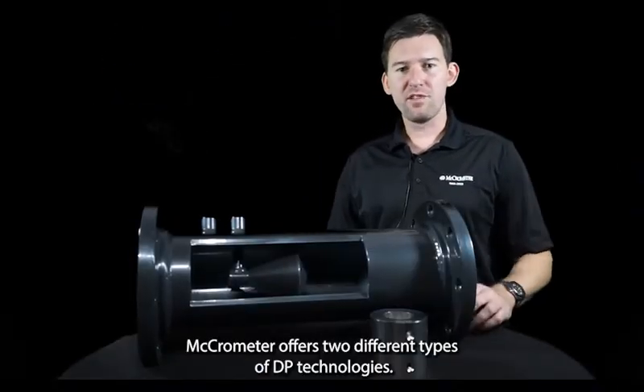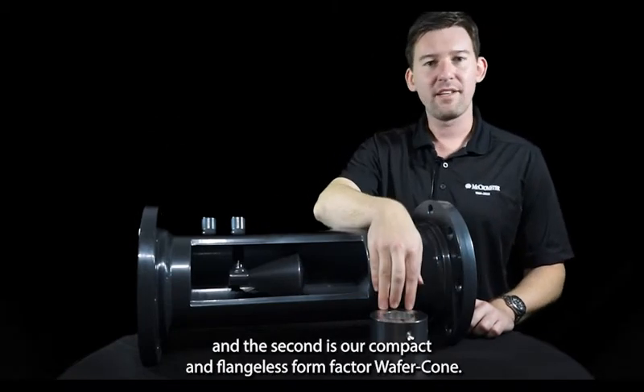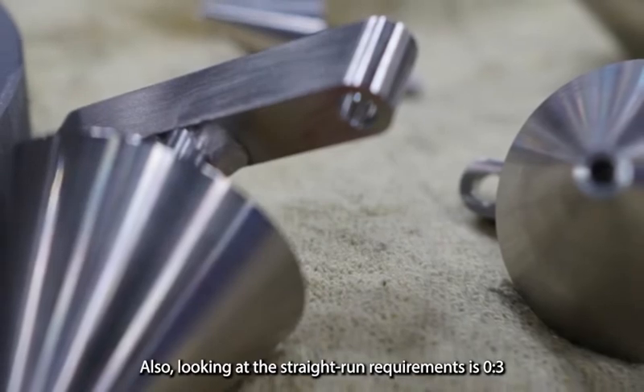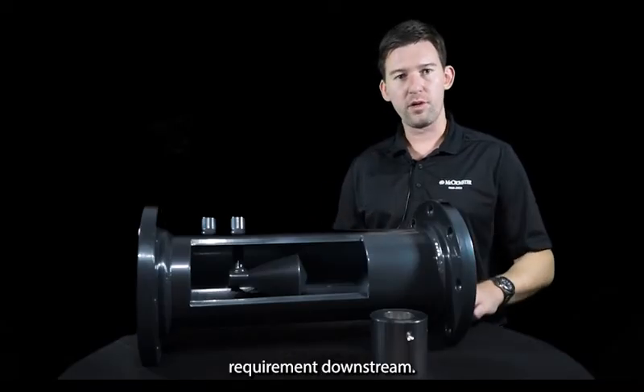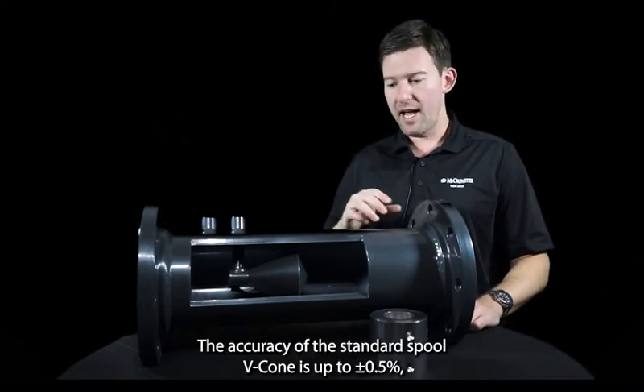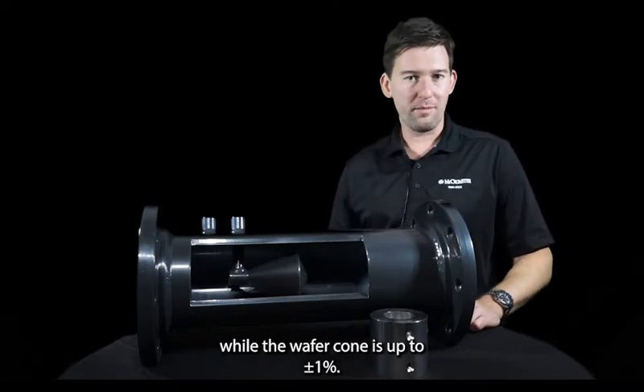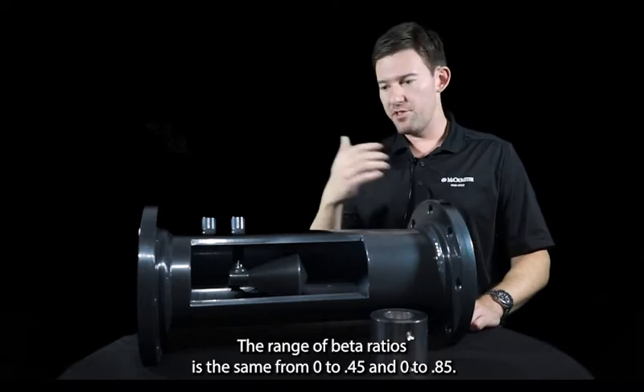McCrometer offers two different types of DP technologies. The first is our standard spooled V-cone, and the second is our compact, flangeless form-factor wafer cone. Both share a number of similarities, including the technology and straight run requirements: a zero to three diameter straight run upstream and a zero to one diameter downstream. The accuracy of the standard spooled V-cone is up to half a percent, while the wafer cone is up to plus or minus one percent. The range of beta ratios is the same for both — from 0.45 to 0.85.